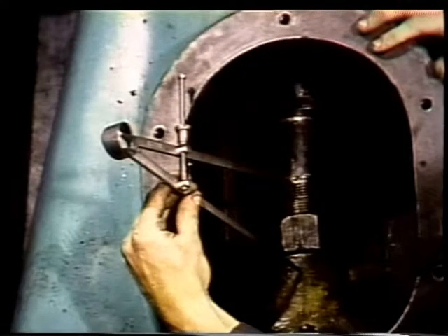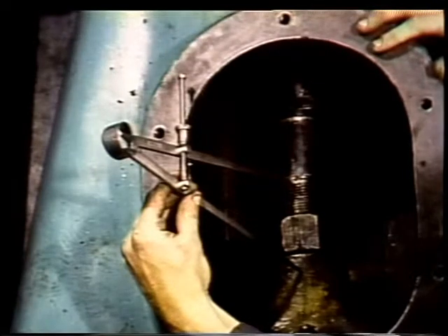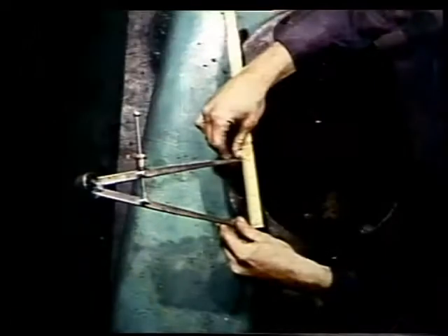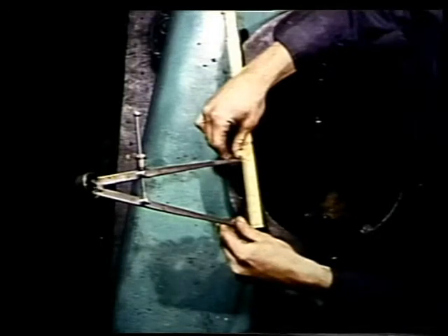With a divider set so that one tip is in each witness mark, you measure the distance between the tips of the divider. This measurement tells you how far the piston rod is screwed into the crosshead. Always write such measurements down. Don't rely on your memory.